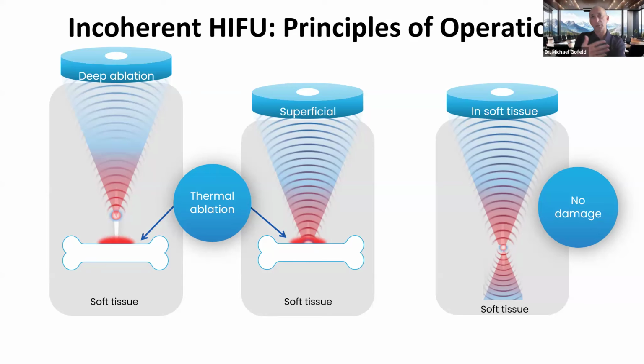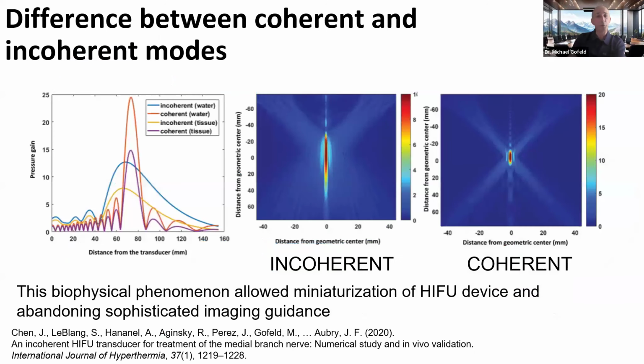Again, it's good, but at the same time it's not really good, because incoherent mode cannot be used in soft tissue. But using incoherent mode gives us the opportunity to miniaturize the device. Instead of a 20 centimeter ring, we can miniaturize it to about 10 centimeters, which makes it more compatible with daily practice. This slide also shows the distance in a geometric center and the simulation with the tissue. This graph shows the peak of coherent versus incoherent. The pressure gain, which may be translated to thermal effect, is way smaller in incoherent versus coherent.